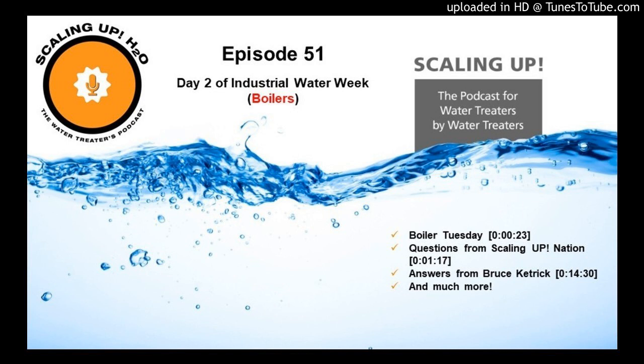Well, in response to Mark Jewell's request, there are two different ways we look at this as far as treatment in boilers. The difference between low pressure and high pressure boilers in most utility applications is at 650 psi. The main reason is that at 650 psi, you're approaching the temperature at which the silica in the water becomes volatile and will carry with the steam. So your chemistry has to dramatically change.